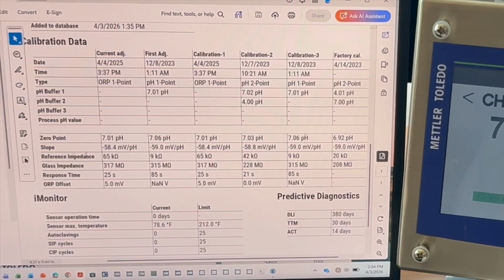Down here we have reference impedance, glass impedance. What are those values on day one? And as the sensor ages, it gets coated, high temperatures stress the glass. Those will be impacted on the reference and glass impedance, and those values will be tracked. And how they differ from the first adjustment is what determines whether the sensor needs to be cleaned, whether it needs to be calibrated, or whether it's actually no longer functional. And we can see the same for the slopes that are captured here and the offsets. If there was a sensor installed in a process and we had a high temperature excursion, that would be captured. You can see a lot of data in here.